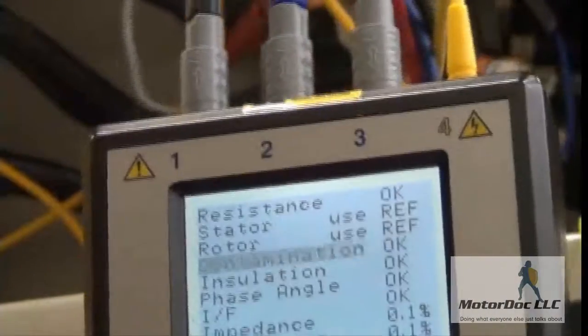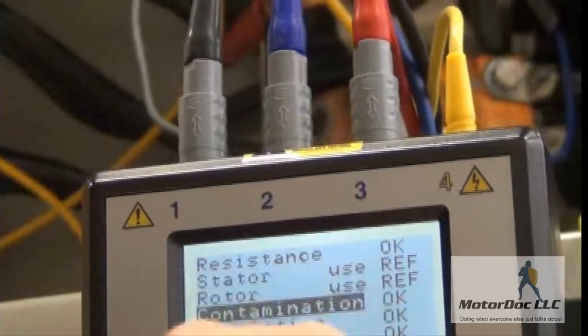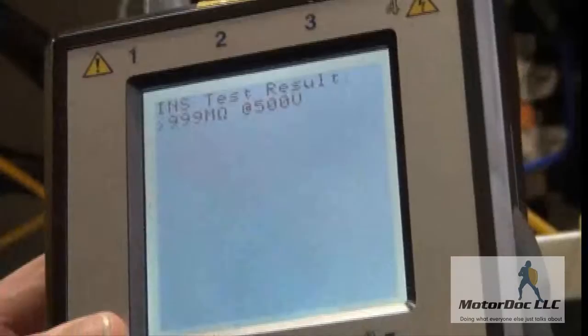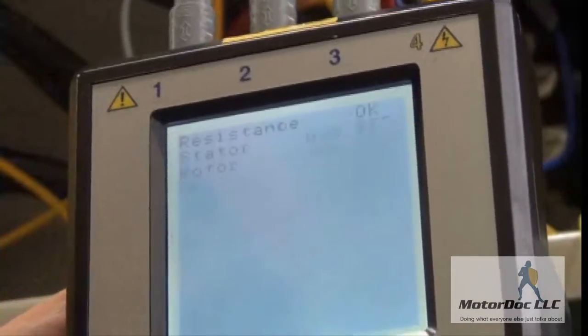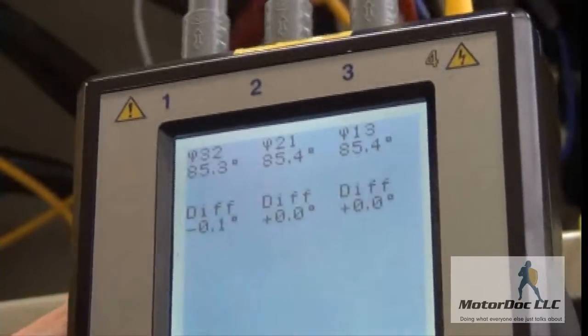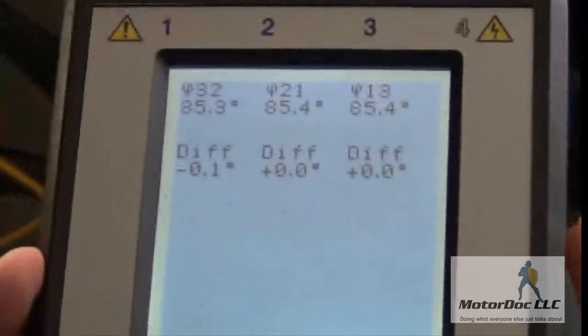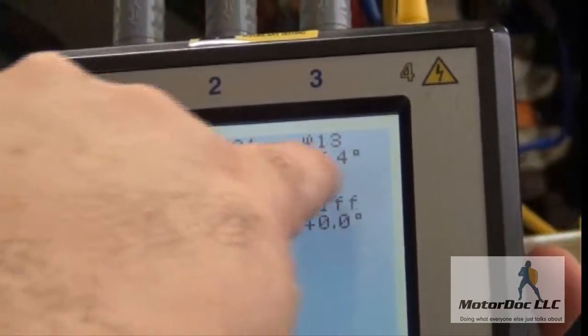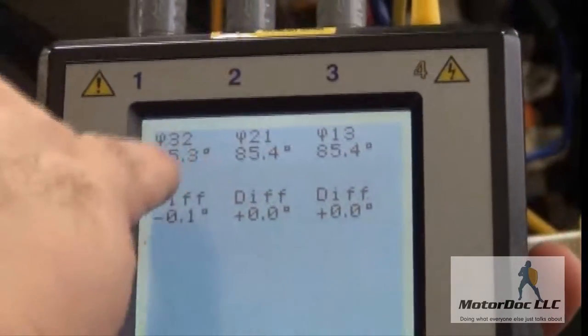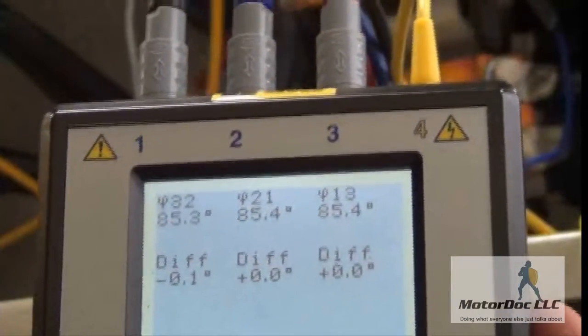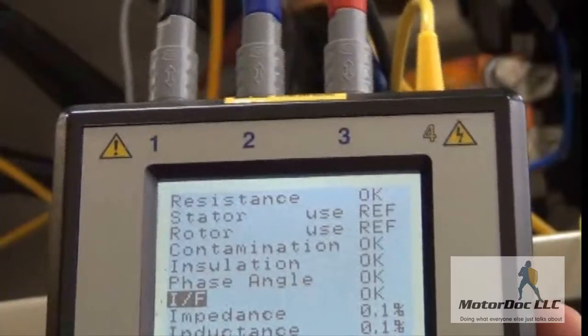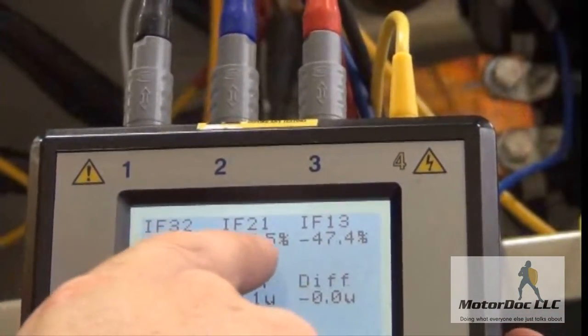On the unit itself, in addition to the equipment giving me test results, it's going to tell me OK, caution, or bad. Coming down to insulation resistance, it's telling me it's greater than a gigaohm at 500 volts. The phase angle — something done on the Alt-Test 4 — goes out to another digit. I'm still looking for plus or minus one from the average, and this is nice and balanced: 85.3, 85.4, 85.4 — very good. I press OK and go to the IF test: minus 47.3, 47.5, 47.4 — well within the plus or minus one range.